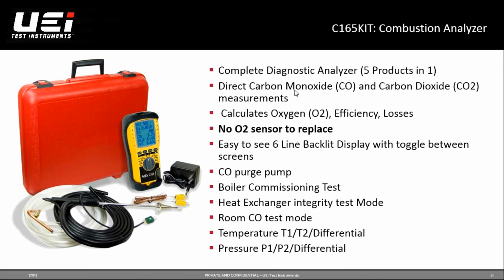The C165 is a really neat unit, and my favorite feature on it is the CO purge pump, especially if you're working on boilers. All too often I've heard of somebody who's hammered a CO sensor, deciding to test it by putting it in the tailpipe of their car. Remember, startup CO could be up to 12,000 parts per million, which exceeds most CO sensors on the market.